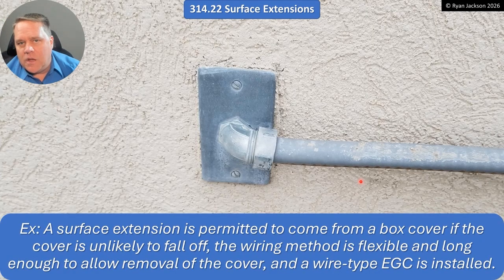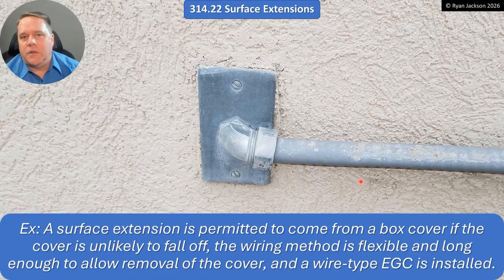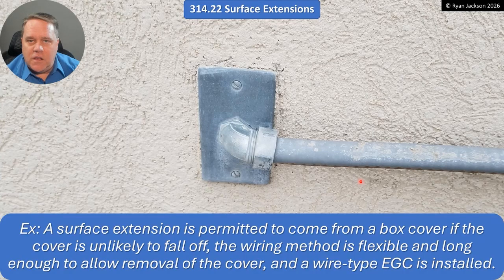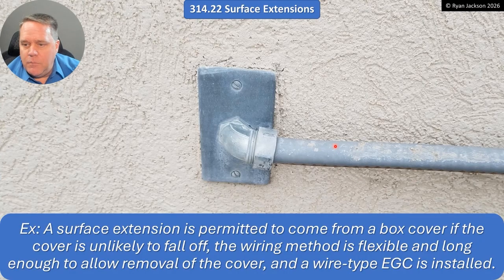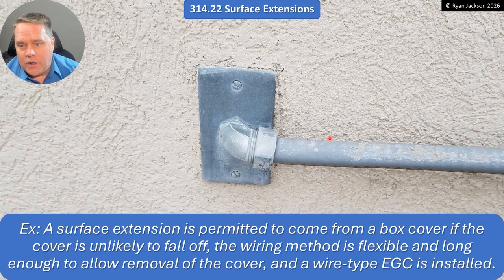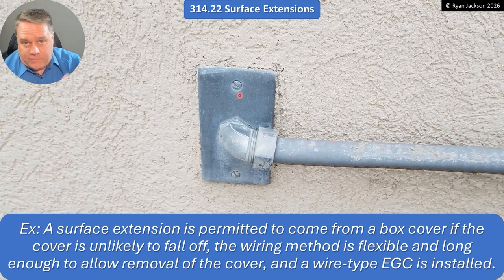There's an exception that says a surface extension doesn't have to come from an extension ring — it can actually come from a box cover. The cover must be unlikely to fall off, the wiring method needs to be flexible and long enough to allow removal of the cover, and a wire-type equipment grounding conductor needs to be in that raceway. So even if I meet the criteria in 250.118 to use liquid-tight as the equipment ground, I still have to have a wire-type EGC in there, because this is a surface extension from the front of a box.